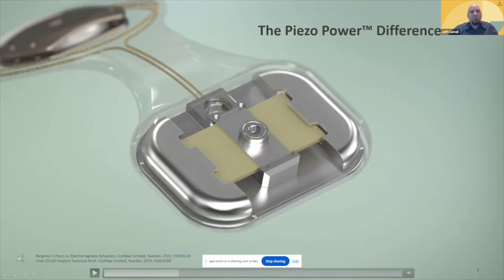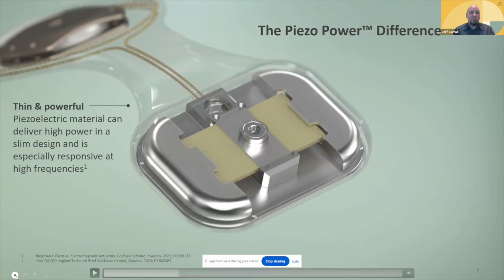On an electromechanical system like the engine that drives the Baha, you clearly can't wear a Baha into an MRI. But even other systems out there that are electromechanical in nature have magnetic materials as part of that engine. So even if it's MRI compatible, we still don't know what the output is. MRIs have significantly strong magnets that affect other magnets, and you just don't know if your output gain will be the same, or the performance, or even if that device might fail, even if it's, again, compatible. But the other end, the magnet end, if you want to go ahead and advance a slide, this is where the change to the OSI 300 relative to the OSI 200 is.